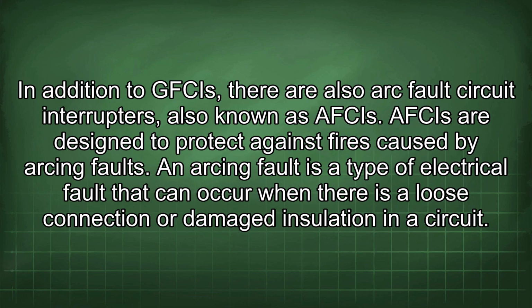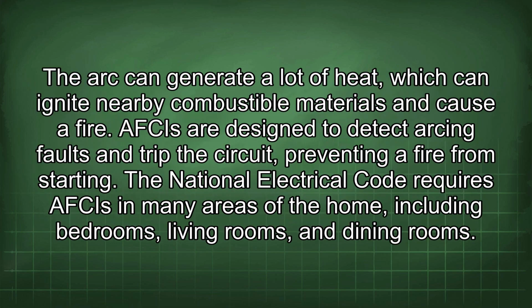In addition to GFCIs, there are also arc fault circuit interrupters, also known as AFCIs. AFCIs are designed to protect against fires caused by arcing faults. An arcing fault is a type of electrical fault that can occur when there is a loose connection or damaged insulation in a circuit. The arc can generate a lot of heat, which can ignite nearby combustible materials and cause a fire. AFCIs are designed to detect arcing faults and trip the circuit, preventing a fire from starting.